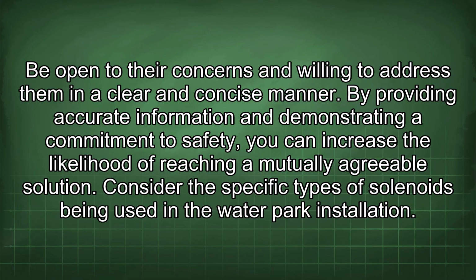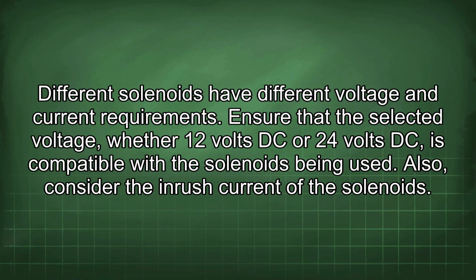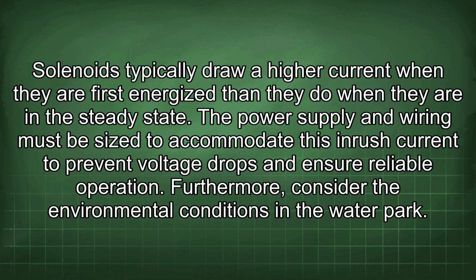Consider the specific types of solenoids being used in the water park installation. Different solenoids have different voltage and current requirements. Ensure that the selected voltage, whether 12 volts DC or 24 volts DC, is compatible with the solenoids being used. Also, consider the inrush current of the solenoids. Solenoids typically draw a higher current when they are first energized than they do when they are in their steady state. The power supply and wiring must be sized to accommodate this inrush current to prevent voltage drops and ensure reliable operation.